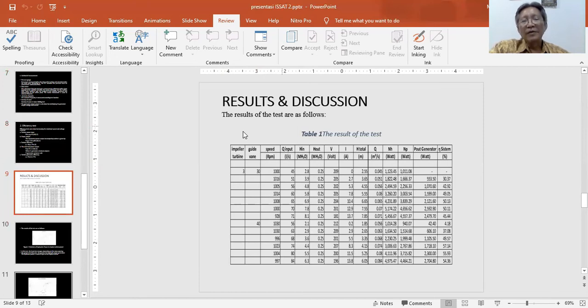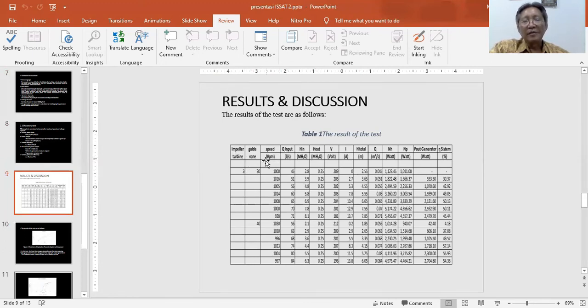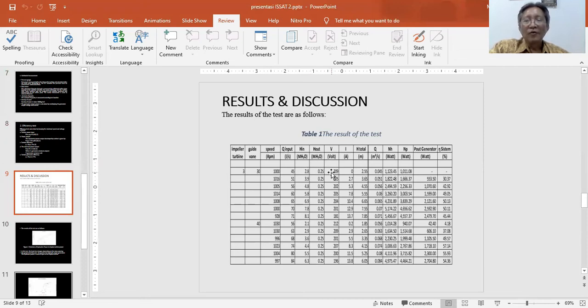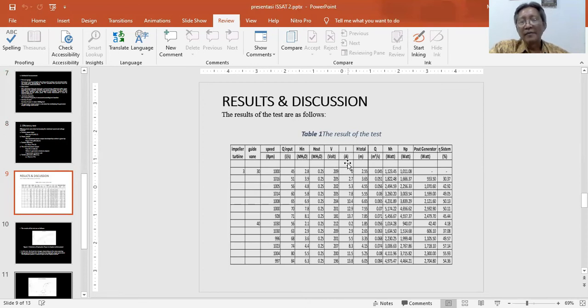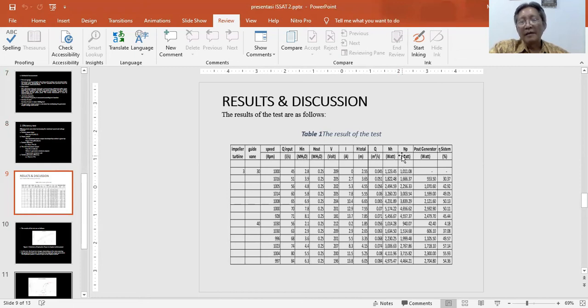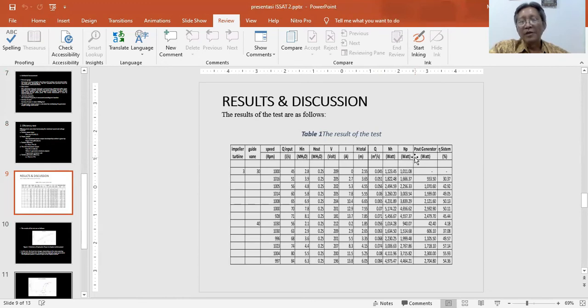According to the test, we have the results shown in Table 1. In this table, we can find head input, head output, voltage, and current. So we can calculate total flow, hydraulic power, mechanical power, and output generator. With these parameters, we can calculate efficiency of the system.